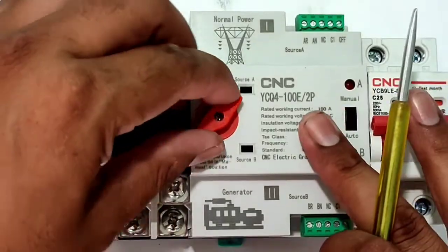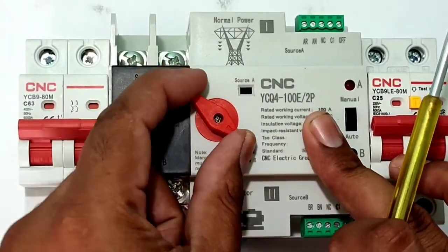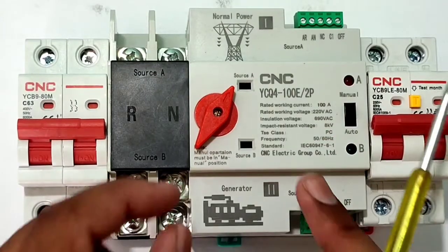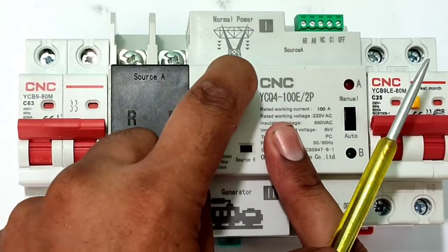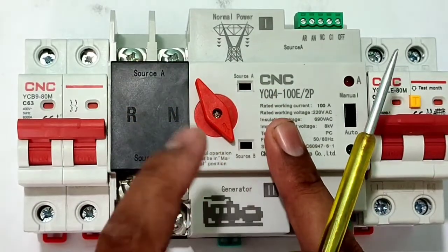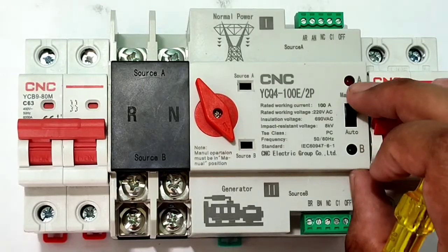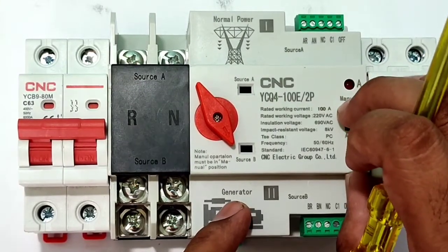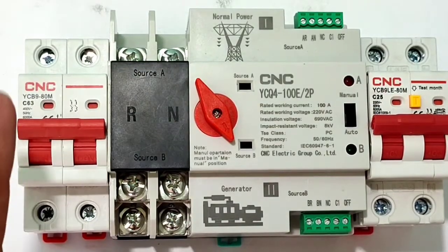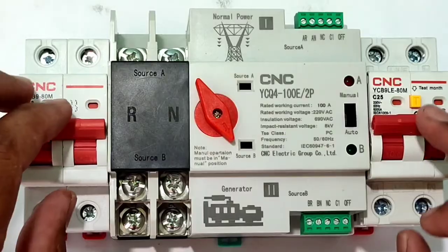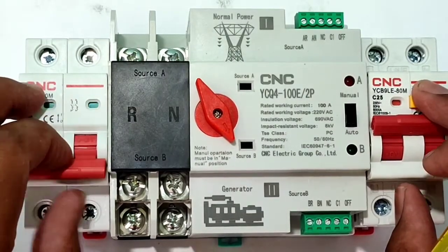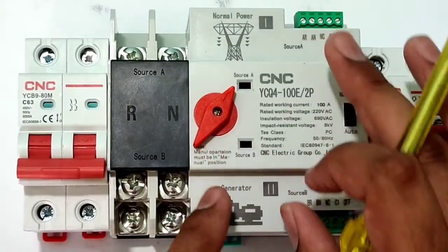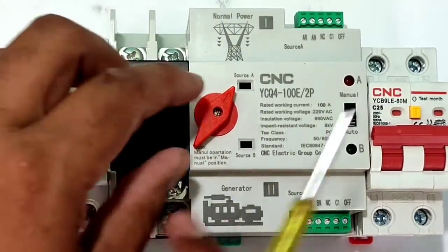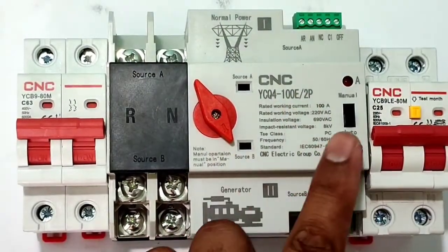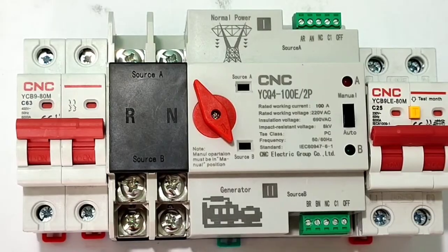Now in this automatic transfer switch, we have two modes, auto mode and manual mode. If you select manual mode, you can change your power supply manually here. If you want to run your load manually on the main power supply, you can select the main power supply. If you want to run your load on the generator power supply, you can select the generator power supply. If you want to transfer your load automatically, you can select auto mode. In auto mode, your load always runs on the main power supply. If your main power supply stops, your load transfers to the generator power supply. If the main power supply comes again, your load transfers automatically to the main power supply. So you can select auto and manual mode here, which is very useful.